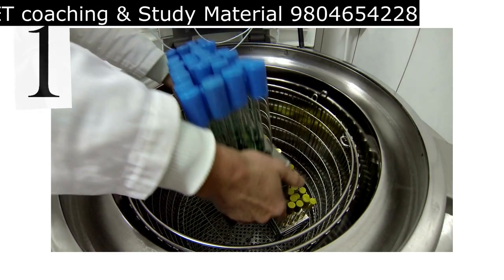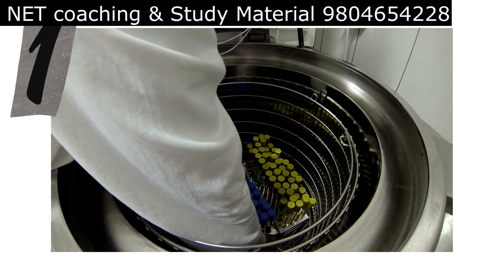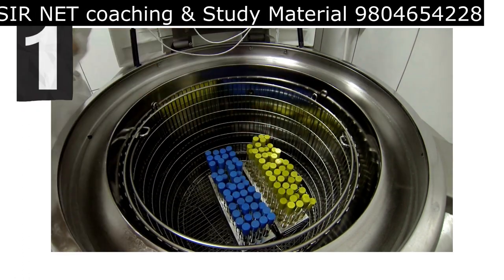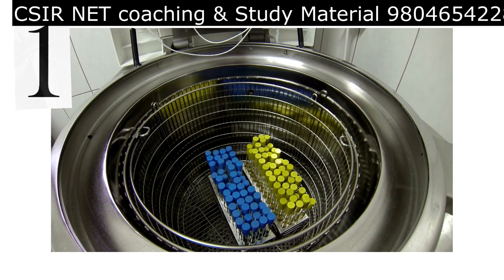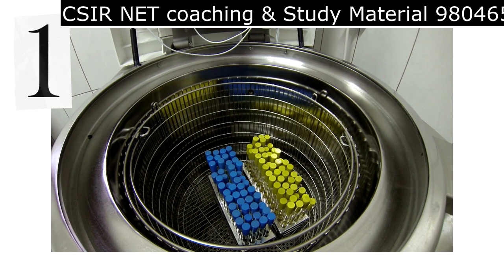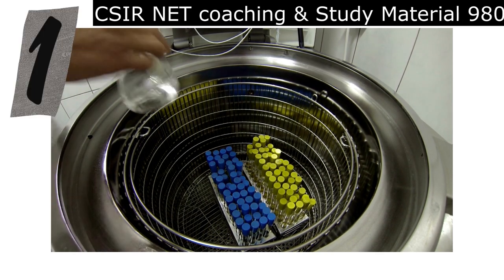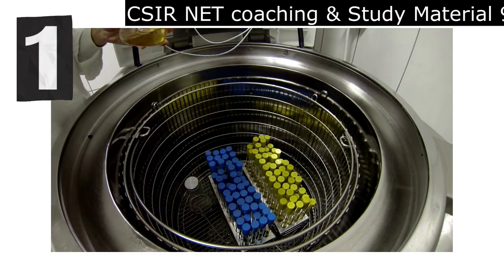Step number one: preparing the autoclave. The very first step is to make sure that the autoclave is in good working condition. Check the water levels, the power source, and make sure the autoclave has been thoroughly cleaned before use.